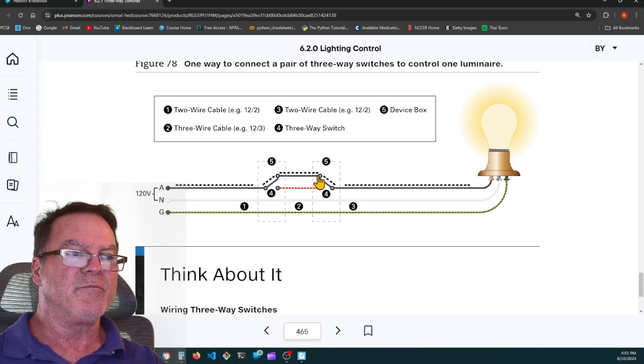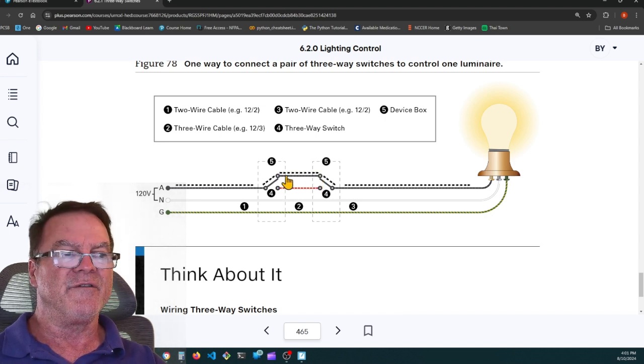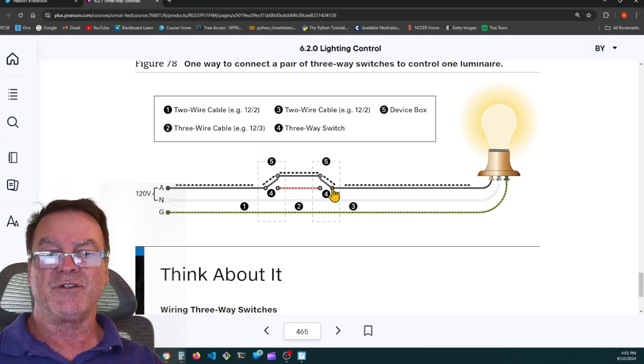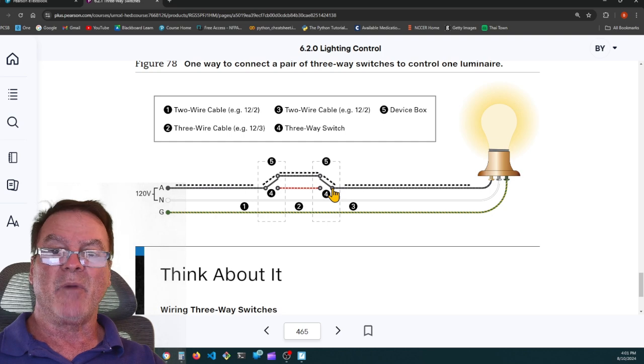And you never put a splice in a traveler. If you have a traveler, it goes from one screw to another screw, and that's it. If you're putting a wire nut on a traveler, you're making a mistake. Don't ever put a wire nut on a traveler. Don't take the hot and go to this common and then bypass the switches and put the same hot on this other switch. If you do that, the switches are bypassed and they will not control the light.